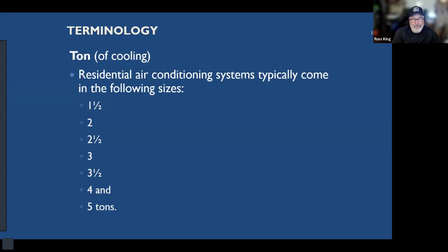And so what the manufacturers have started doing is getting rid of the half-ton increments. It's really bizarre. There's no longer a 1.5 ton. It goes right to 2 ton. There's no 2.5 ton. It goes to 3 ton, and no 3.5 ton, four. So there are only even number increments: 2, 3, 4, 5 ton, or 1, 2, 3, 4, 5 ton. It's getting kind of weird from what it used to be back in the day, but this is still fairly standard.